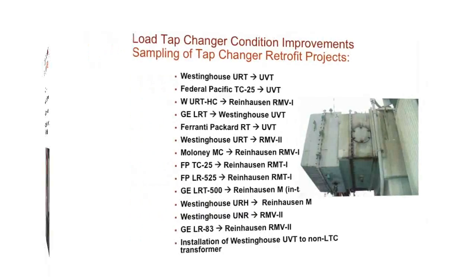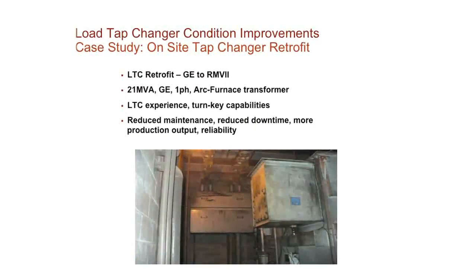Talk about a retrofit we did on a GE to RMV2. It's on a 21 MVA GE single-phase transformer. This was an arc furnace transformer, so it saw a lot of tap changes quite frequently, and the tap changer just basically hit the end of its useful life. So it was better to do the retrofit. Ended up with reduced maintenance. This is a picture of what it looked like previously, and then when it looked like when we were done.